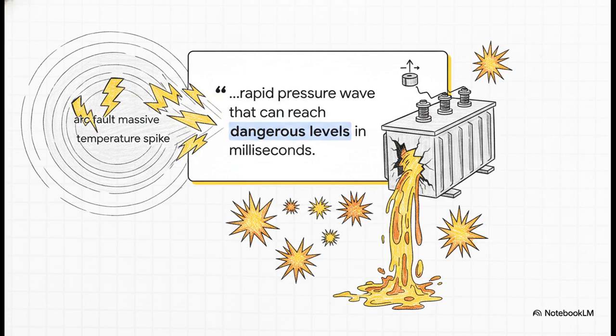You see, an arc fault creates a rapid pressure wave that can reach truly dangerous levels in a matter of milliseconds. Without a way to instantly relieve it, that massive temperature spike we just talked about creates a pressure buildup so intense it'll rupture the thick steel tank, spill burning oil everywhere, and set off a massive, uncontrollable explosion.